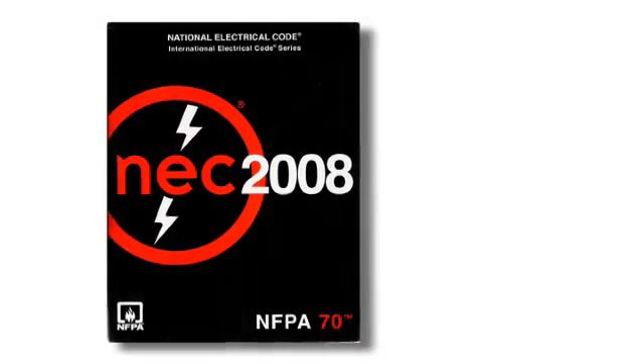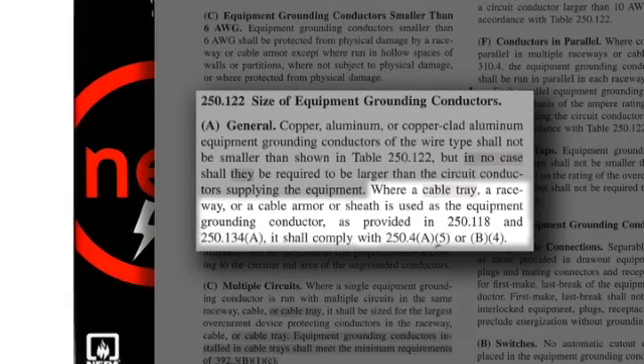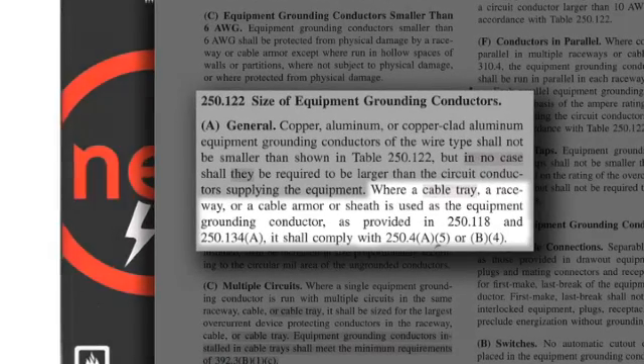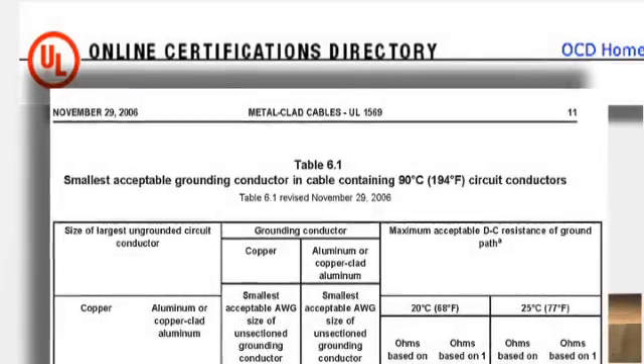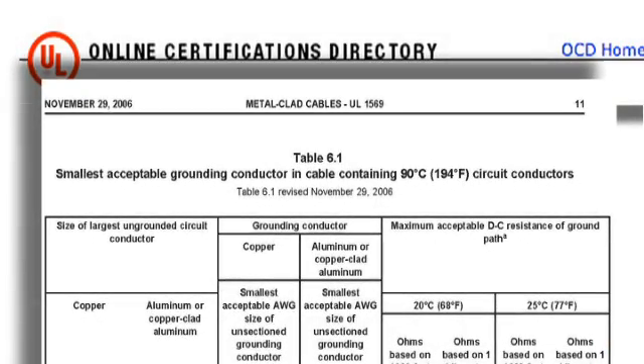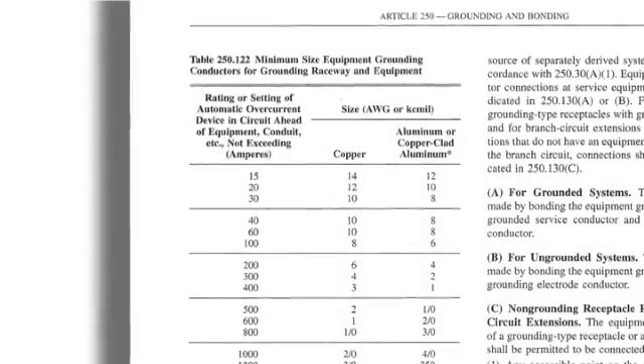NEC Section 250.122 also allows the cable armor or sheath to serve as a ground path for the cable if it provides a low impedance effective ground fault current path, just like a conventional equipment grounding conductor. Now let's take a look at the UL1569 MC cable standard. Table 6.1 in the UL standard specifies the ground path performance requirement for MC cable based on the NEC requirements. In fact, the table looks a lot like NEC Table 250.122.